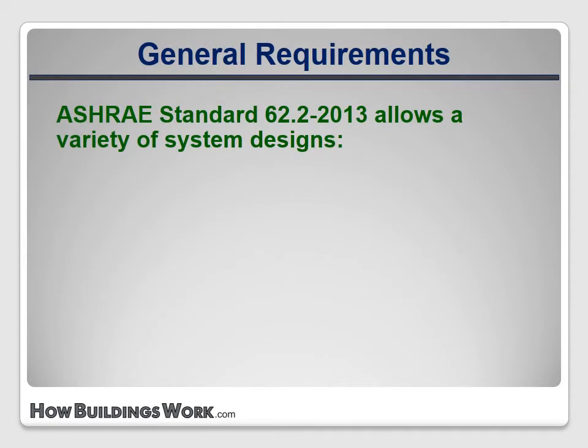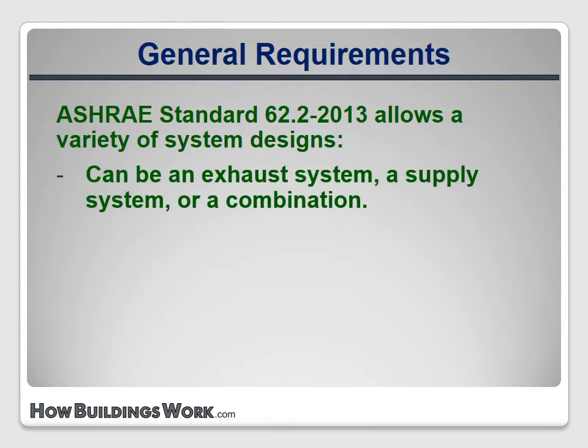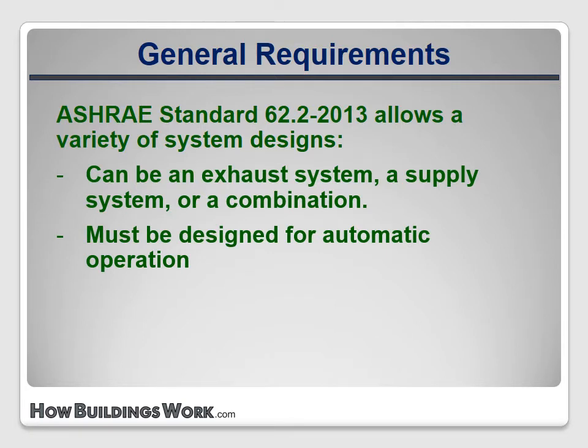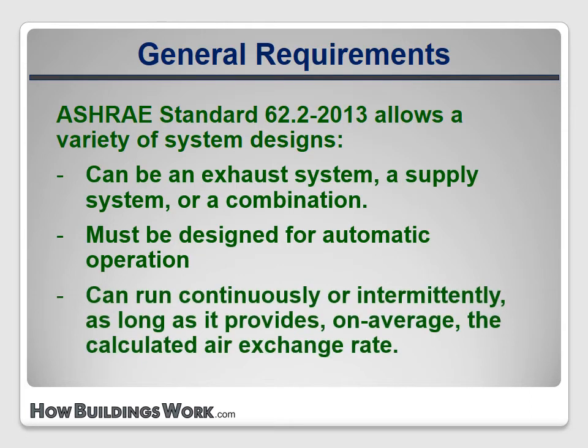ASHRAE 62.2 allows a wide variety of approaches to provide air exchange in the building. The system can provide the air exchange using exhaust fans, supply fans, or a combination of both. It must be designed for automatic operation, meaning it must run without the need for the occupants to regularly turn it on and off with a switch. The system can either run continuously or intermittently, automatically turning itself on and off as long as the average air exchange rate meets the calculated requirement.